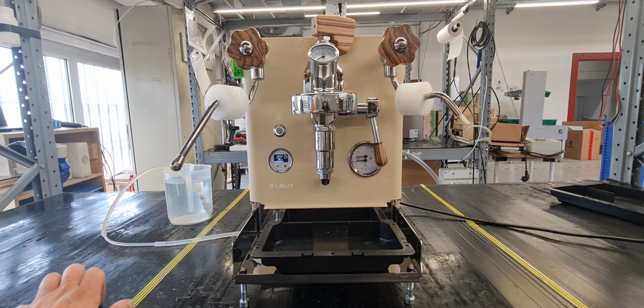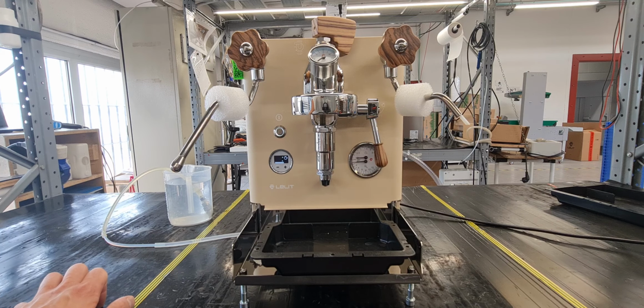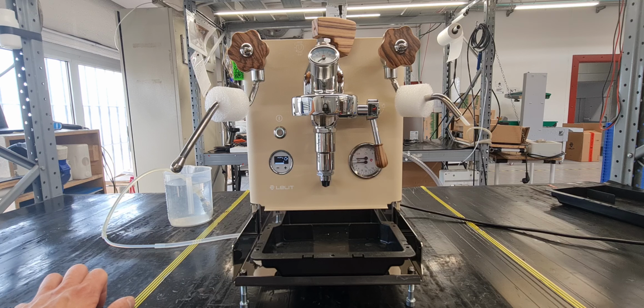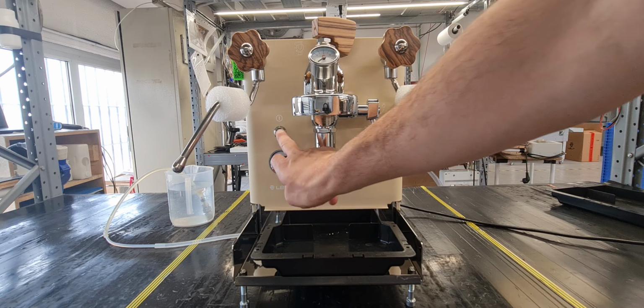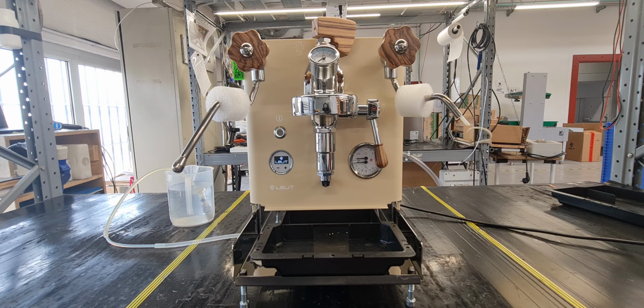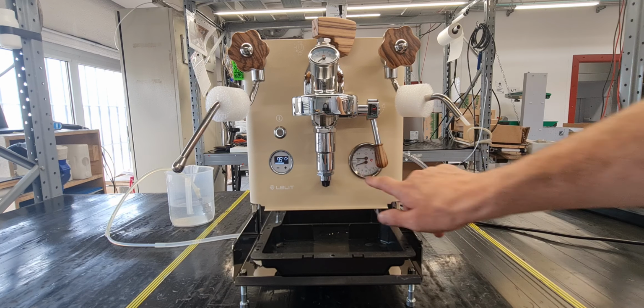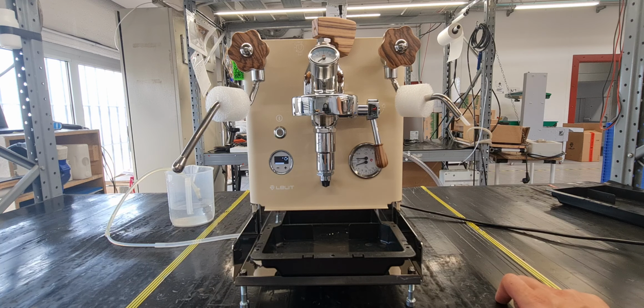Good morning. In this video we are simulating a water refilling problem on a Bianca PL162T. 3, 2, 1, we turn on the machine and the pump starts running to refill the steam boiler. When the boiler is full of water, you can see the pressure gauge rise up the pressure.